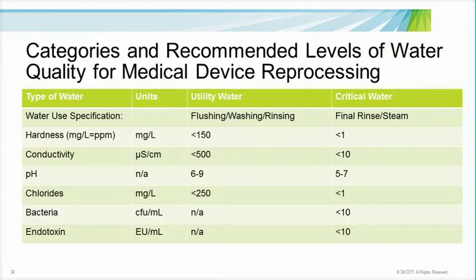This chart is the acceptance criteria for each category of water from TIR 34. It is a very nice chart which shows what the utility water and critical water will be used for, and also the specific acceptance criteria that is very important during each water use specification and type of water acceptance criteria. The appropriate hardness of utility water should be less than 150 milligrams per liter, and less than 1 milligram per liter for critical water.